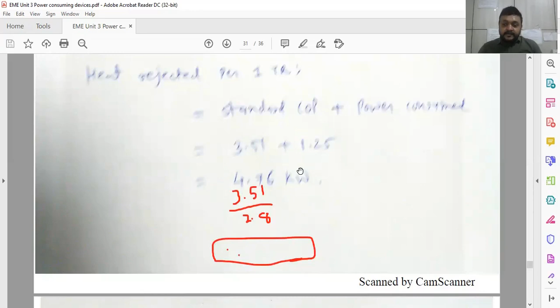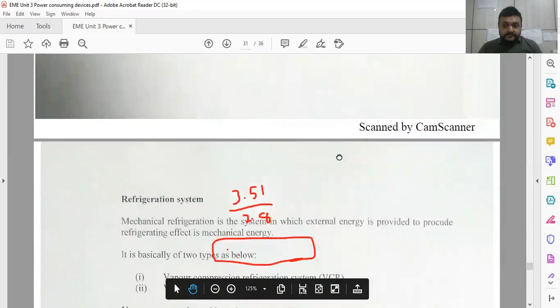So based on the heat rejection, we can see the actual amount of refrigerating effect produced. So heat rejected per ton is equal to standard COP, that is 3.51, plus power consumption. So standard COP is actually the heat used to convert 1 ton of water into ice. So that is the standard 3.51 plus what is our power consumption? 1.25. So in total, 4.76 kilowatts is the total heat rejected during the refrigerating effect. So this is the way we can find out the power consumption and heat rejected in the refrigeration system. Okay, so this is about the refrigeration system.